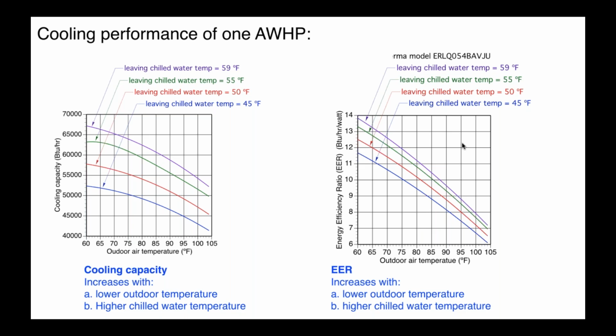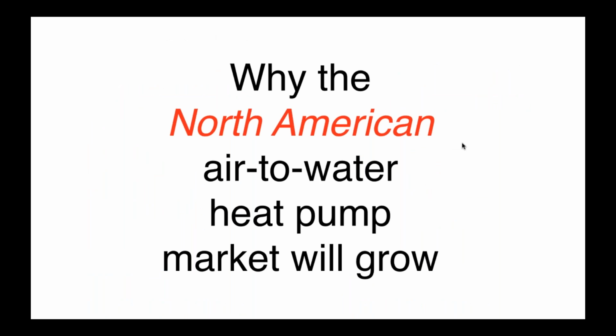So again, if you can design a chill water cooling system and work with maybe 50 to 60 degree water versus 40 to 45 degree water, you're going to see a benefit in terms of better cooling capacity and better efficiency.